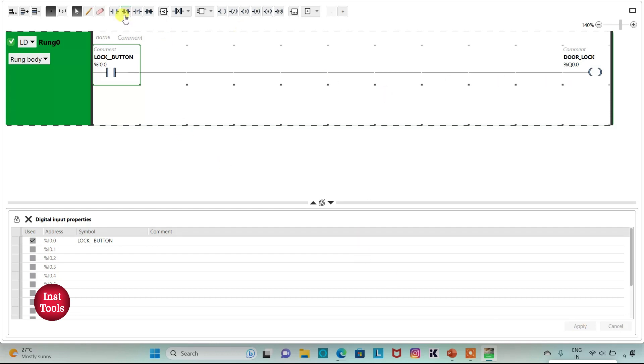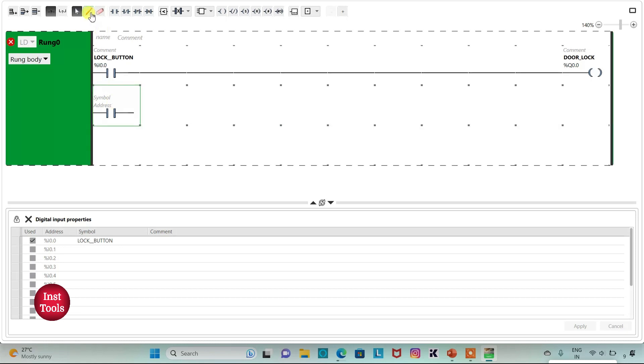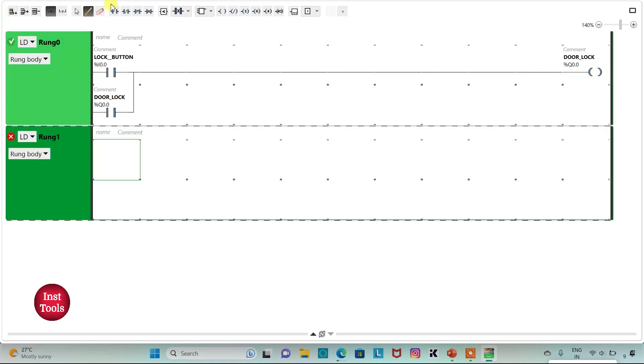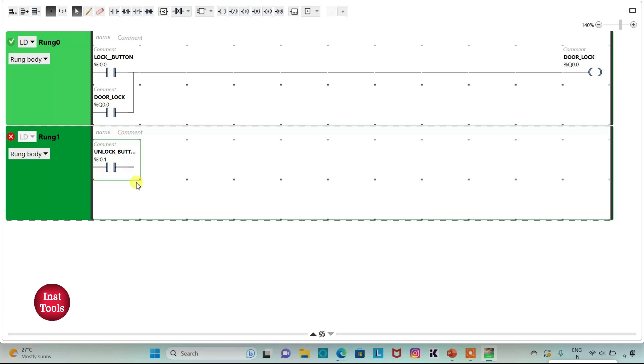Then I will add a normally open contact connected in parallel, and assign the same address as door lock, Q0.0, to latch it. So when the lock button is pressed and released, the door will be locked. Then I will add a new rung and insert a normally open contact, assigning address I0.1 with symbol 'unlock button'.